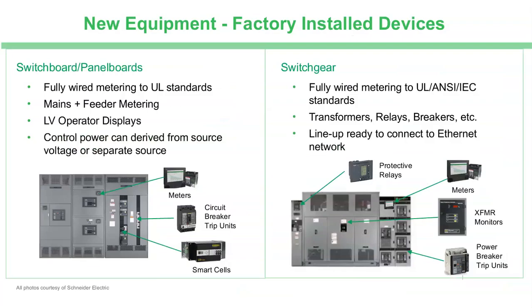So just a quick look, if we do have equipment that's being supplied with these meters, this is where you would see them. On the left-hand side, this is your low voltage equipment, or basically 600 volt and below. So you normally would see your individual meters, you'd have your communicating trip units, and then in some cases you may have these smart cells that are plugged in like breakers that actually include metering. On the right-hand side, we've got medium voltage gear or switchgear. There we would be looking at protective relays. Again, you'd have individual metering. We would be able to monitor the temperature of the transformers. And then on the low voltage side, again, you'd have meters and trip units.